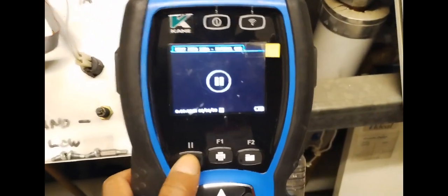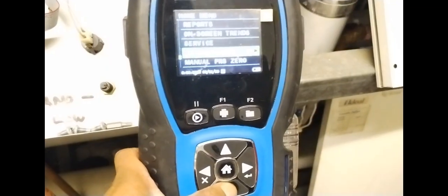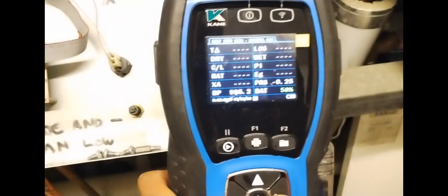And then onto the pressure test. We're going to do our typical drop test on the gas valve. It's good to zero your manometer beforehand. Zero our pressures. Gonna open our gas valve.